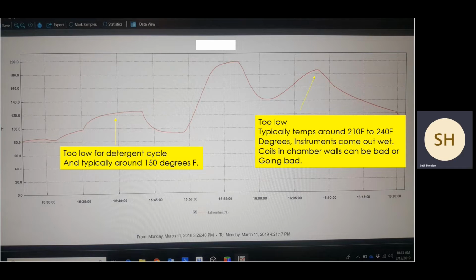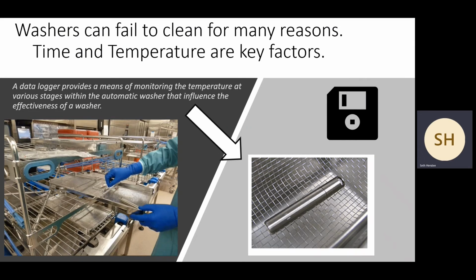And that's because that temperature is typically a little bit higher than what it is there. So washers can fail to clean for many reasons, but time and temperature are usually your key factors. So something like a data logger, which is from the plot that I just showed, can monitor this, especially with washers that don't come with printout tapes anymore, and there's many of them that don't. You actually would have to stand there and watch the cycle on the display itself. This is a way to stick something in, walk away, plug it into the computer, and then look at the cycle objectively after it's done.